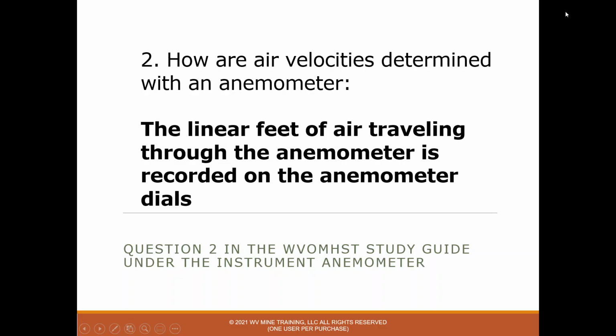Question 2: how are air velocities determined with an anemometer? The answer is the linear feet of air traveling through an anemometer is recorded on the anemometer dials. The velocity is just distance per time, and we're always looking for feet per minute. The linear feet of air flowing through turns the blades on the anemometer and turns the dials, and that way we can determine the linear feet of air traveling, always for 1 minute, so we get linear feet per minute.